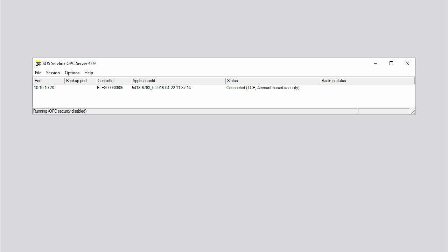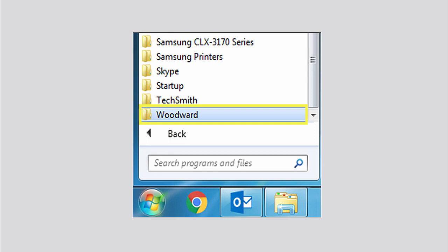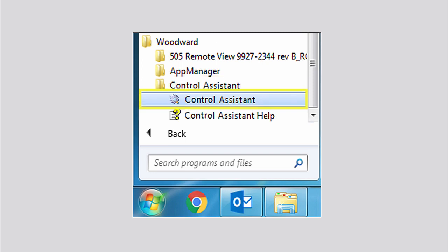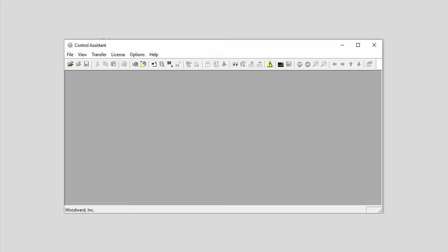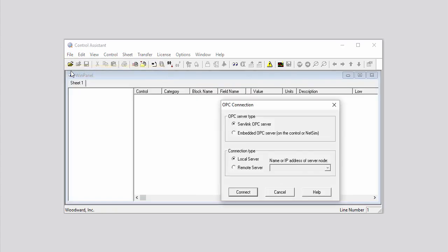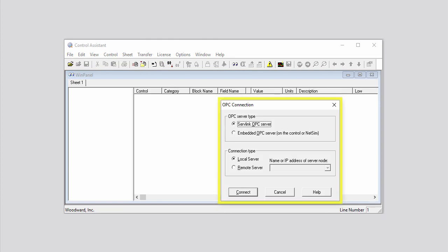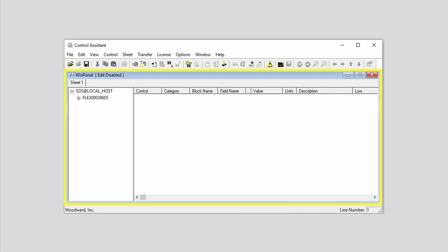Now you need to open Control Assistant. Click the Start button, click All Programs, click to open the Woodward folder or, if applicable, the alternate folder you specified during installation. If applicable, click to open the Control Assistant folder, then click Control Assistant. To use Control Assistant to receive and load a tunable configuration file from your controller, either click File on the menu bar and then click New Win Panel on the drop-down menu, or press the Control and W keys on your keyboard. In the OPC connection dialog box that opens, verify that Servlink OPC server is selected as the OPC server type and that Local server is selected as the connection type, then click Connect. The Win Panel window opens within Control Assistant.